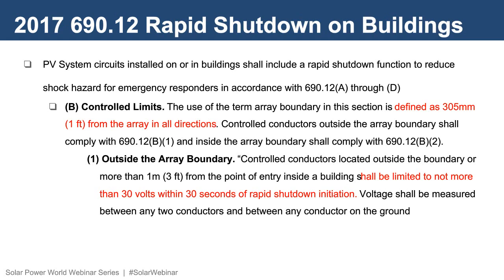The 2017 version of rapid shutdown is far more detailed and has more stringent requirements when compared to the 2014 version. The term controlled conductors is the same, except now there are 2 distinct areas with different controlled values. 690.12(B)(1) refers to conductors outside the array boundary, and 690.12(B)(2) refers to controlled conductors within the array boundary. Controlled conductors outside the array boundary must be limited to 30 volts or less in 30 seconds.